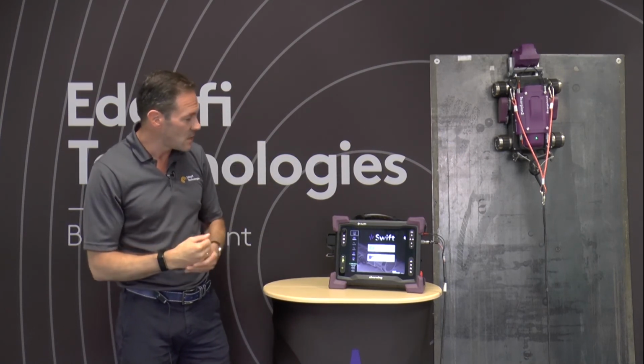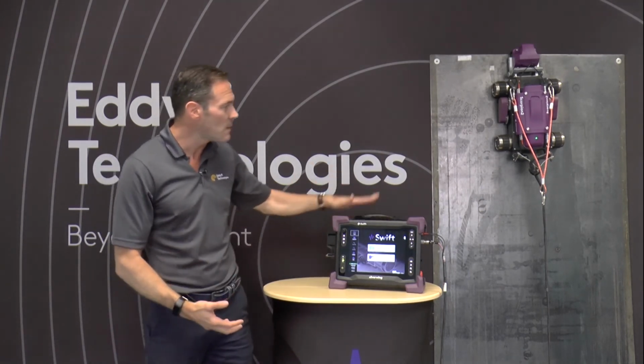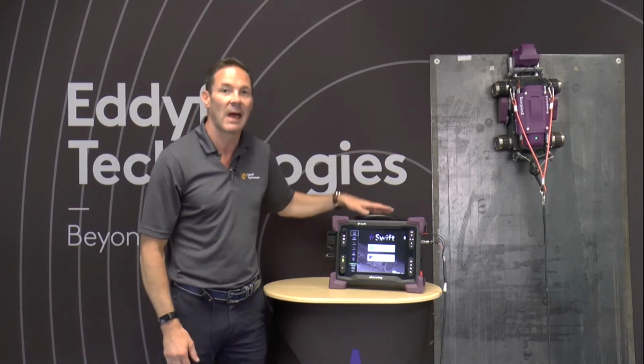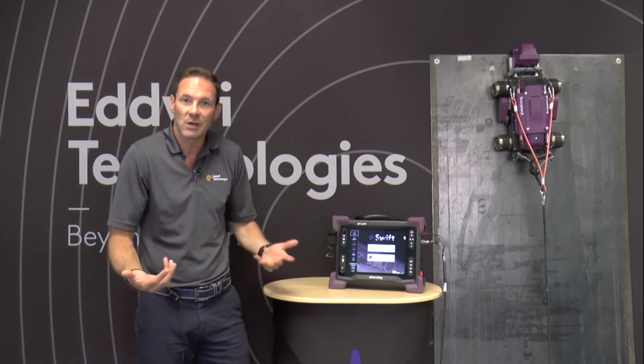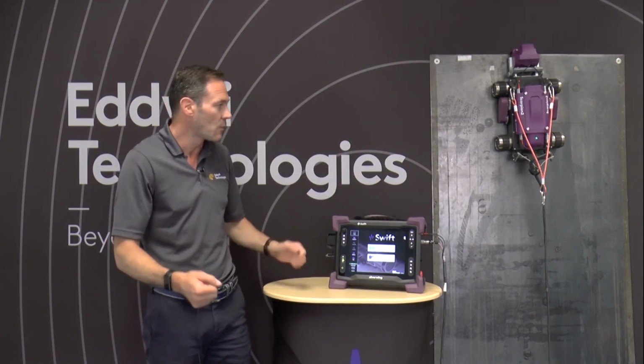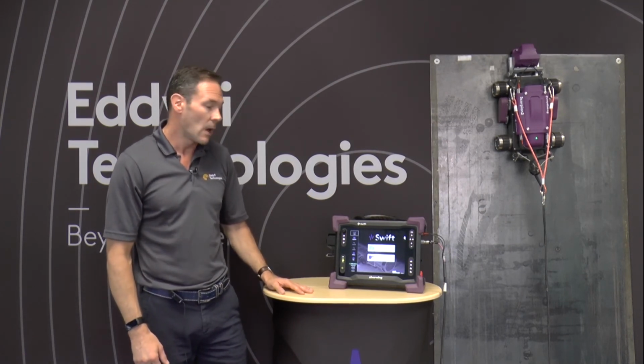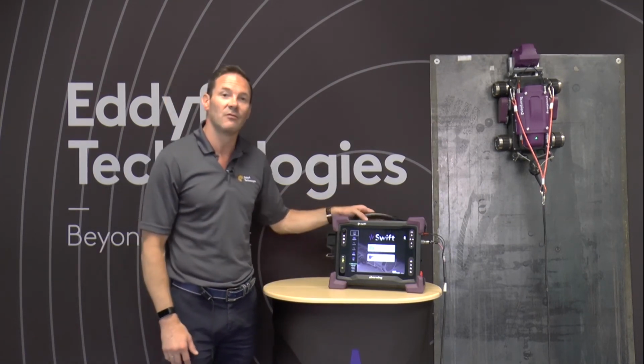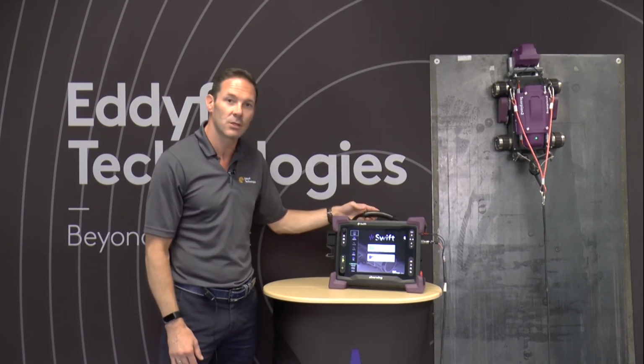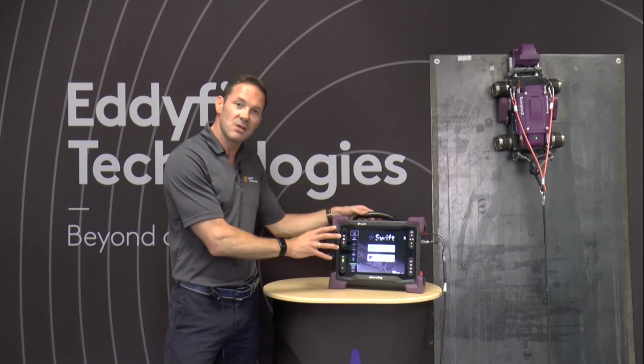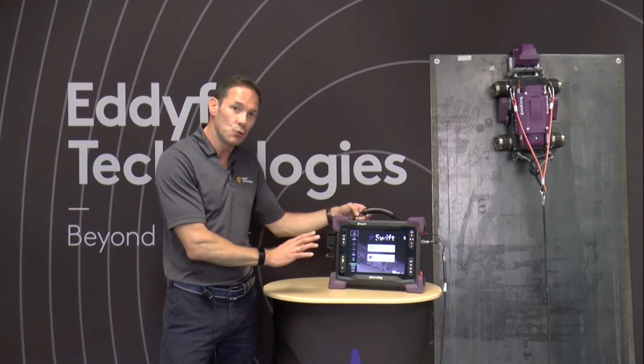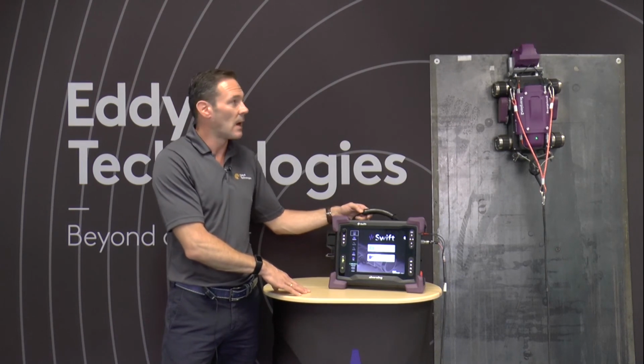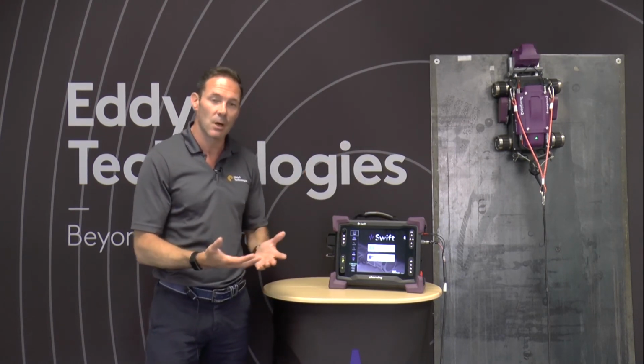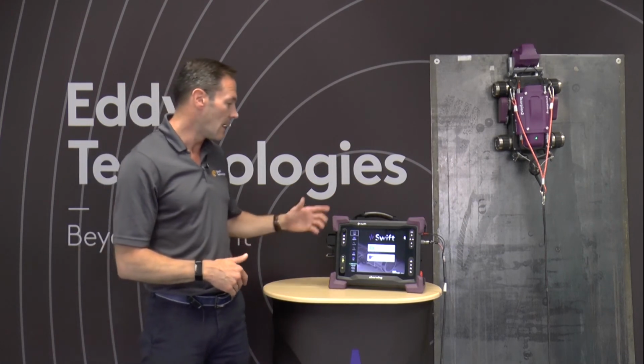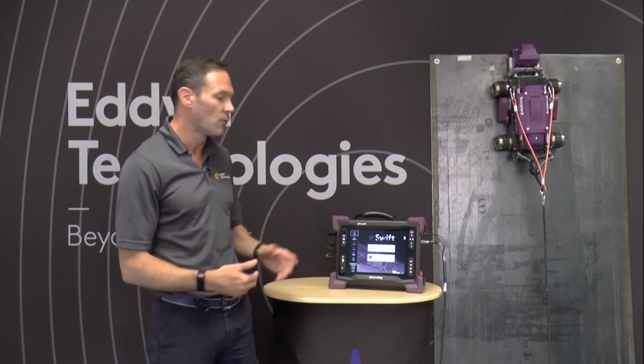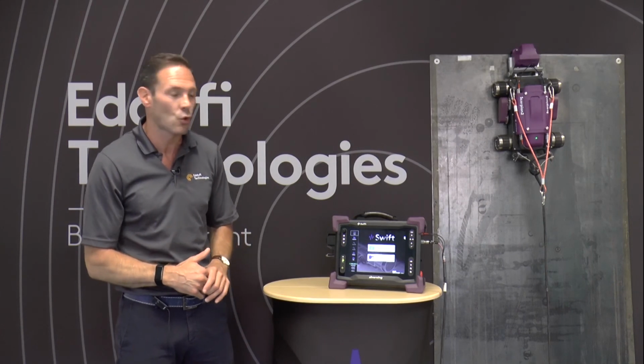The other benefit, I think, is the design of the system. We only basically have 2 components, a data acquisition unit and a crawler, which is connected with the reel. 3 components, easy to deploy, quite easy and lightweight to carry. I think what's also important is that the UT quality of this system is far better than the older system. The UT card in this unit is a new design with state-of-the-art electronics. We have stabilized the probe, so the probe pressure is much better, much more stable. You get a much clearer signal, and all in all, the signal to noise ratio for the unit is far better than the older Scorpion 1.